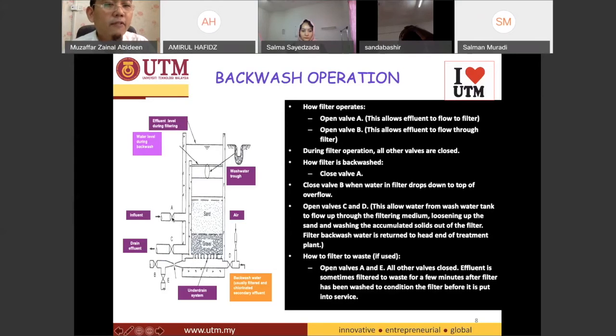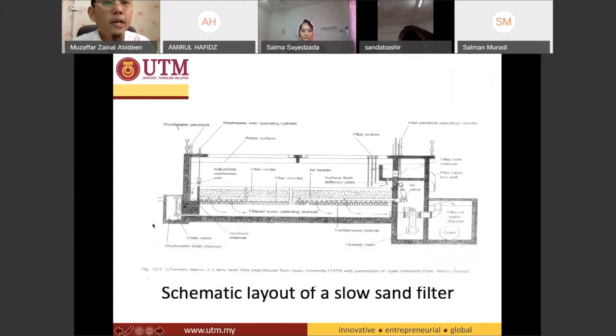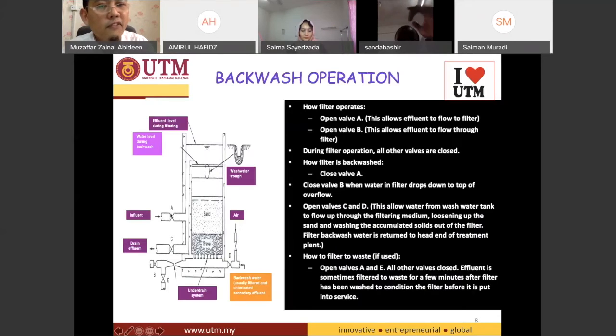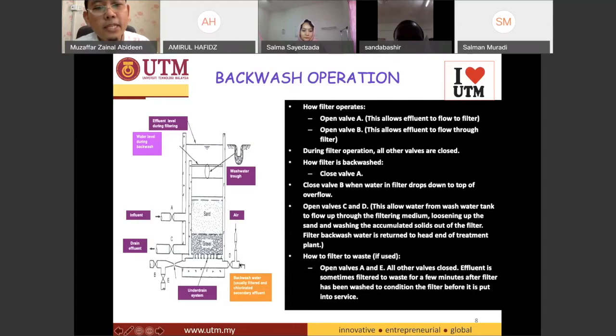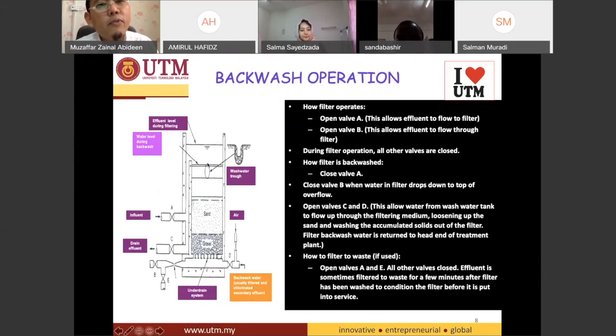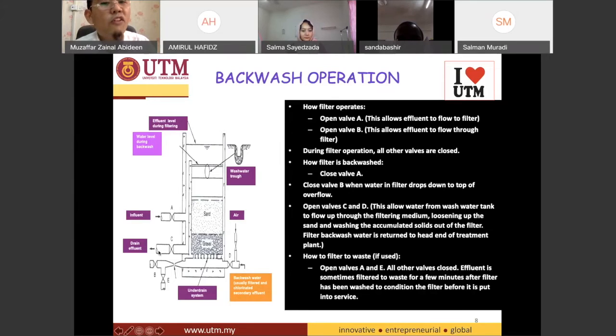To clean the filter, we need to close valve A, valve B, and valve E. Then we have to open valve C and D. The small amount of water that we kept is then used to travel through the filter in the opposite direction.